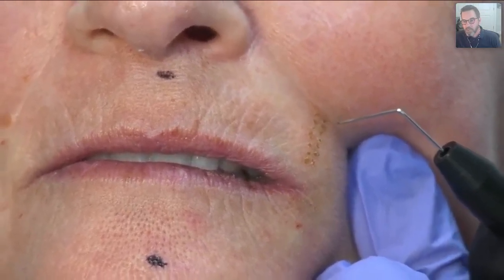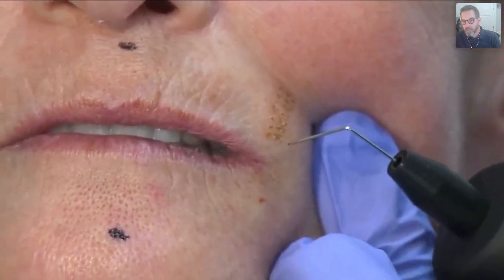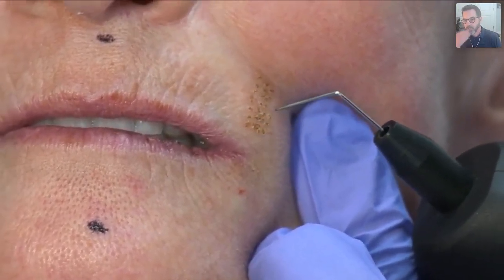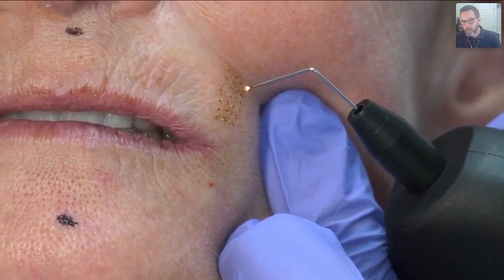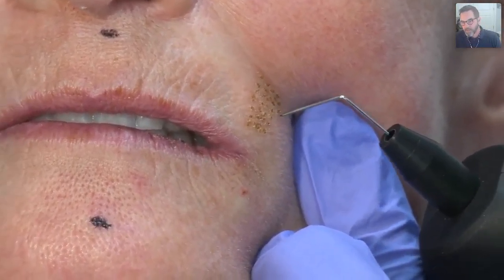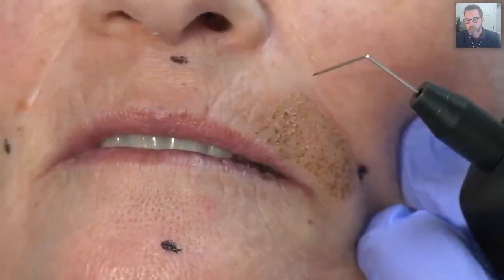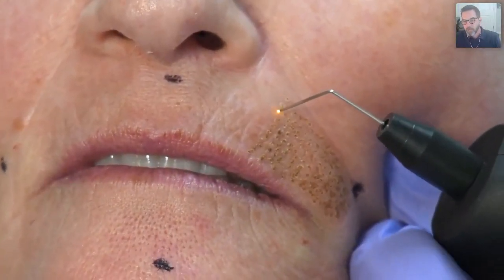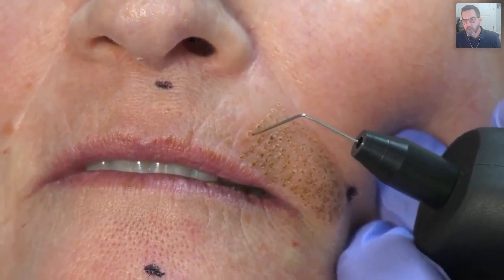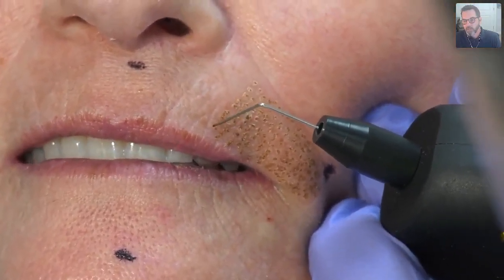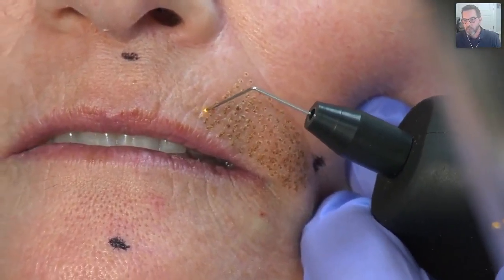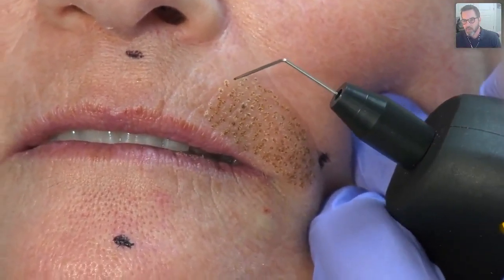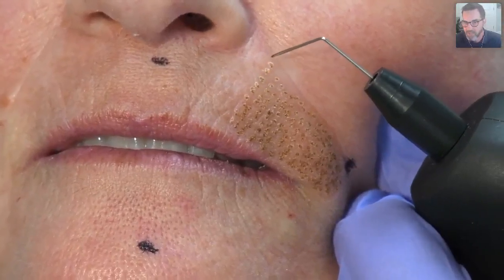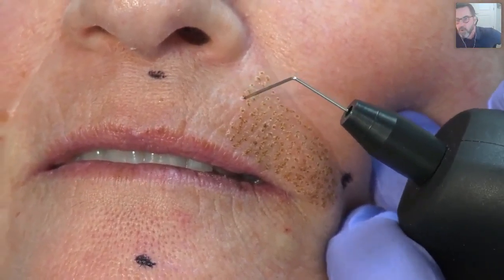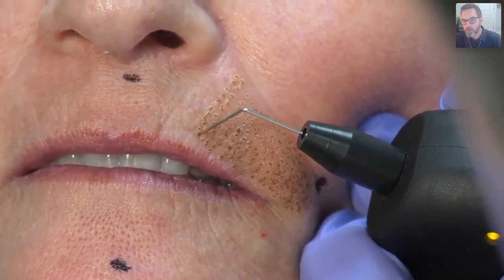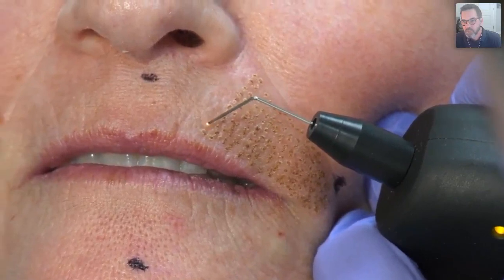And again, the physician here that's delivering the energy, this is a very good example of what I would call the 1-1-1 technique. So you can appreciate that these are about 1 millimeter apart, that they're on the tissue for 1 second or less, really. This is utilizing low power. And you've got the probe about 1 millimeter away from the surface of the skin. So you're never actually touching the surface of the skin. You will begin to see over time with large surface areas a buildup of carbon crust. You can kind of see the blackening at the tip of the probe. You may need to, from time to time, wipe that off because you'll notice that your energy delivery just doesn't seem to be as effective.